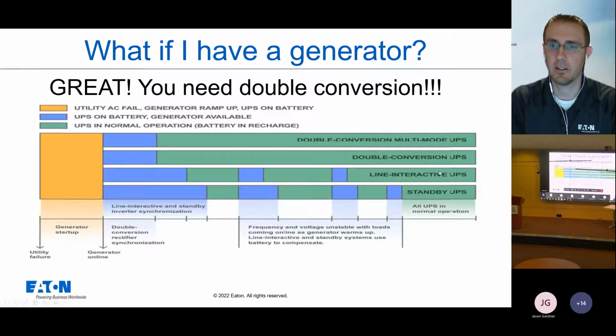As you get down into line interactive, or certainly a standby UPS, as a generator is coming online, you can see by the different color codings here, the utility failure, you're going to go to UPS on battery. With a double conversion, that's only going to happen once, and there's zero transfer time. When you get into line interactive and standby UPSs, it's going to do that a couple of times because there will be fluctuations as that generator starts up to come online, as different things start to take advantage of the generator power.